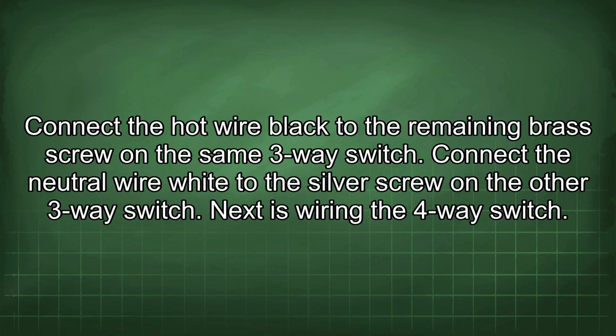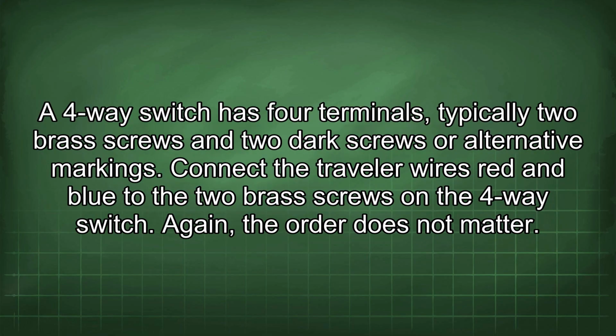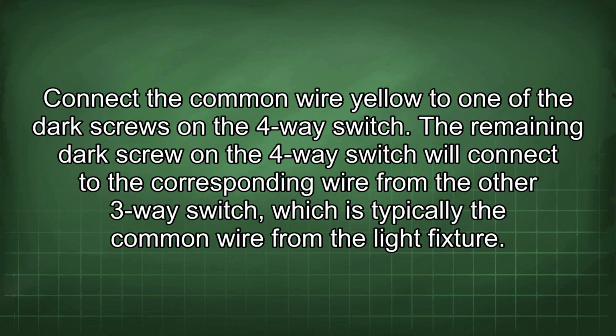Next is wiring the 4-way switch. A 4-way switch has 4 terminals, typically 2 brass screws and 2 dark screws or alternative markings. Connect the Traveler wires red and blue to the 2 brass screws in the 4-way switch. Again, the order does not matter. Connect the common wire yellow to one of the dark screws in the 4-way switch. The remaining dark screw on the 4-way switch will connect to the corresponding wire from the other 3-way switch, which is typically the common wire from the light fixture.